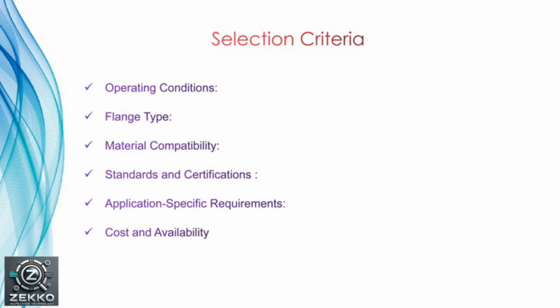We will see the selection criteria for the spiral wound gasket. While selecting a spiral wound gasket, several criteria shall be considered to ensure the gasket performs effectively and reliably under the given operating conditions. So the first selection criterion is operating condition. The first parameter is temperature. Ensure the gasket material can withstand the operating temperature of the application. Spiral wound gaskets are typically suitable for temperatures up to 1000 degrees Celsius depending on the filler material. The second parameter is pressure. Always verify the gasket pressure ratings align with the system requirement. They can handle pressures up to 400 bar or more.